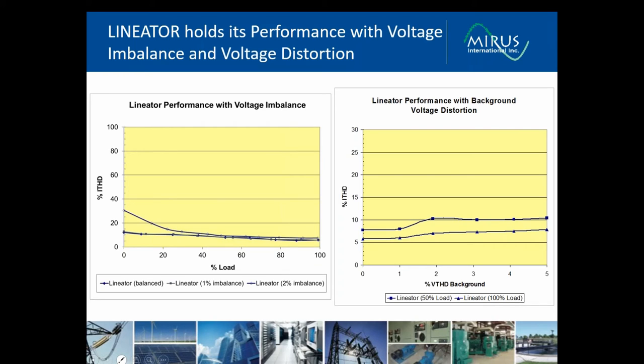We talked about the real world guarantee. Here we have, again with voltage imbalance, the performance of a filter with balanced or 1% imbalance. You can see here's our performance waveform. Light loads, THD, all the way up to full load. As we introduce 2% imbalance, there is a drop off, but it still performs within our performance guarantee, even at those higher voltage imbalance levels. And with background voltage distortion, you can see there is some drop off in performance, but even with 5% background voltage distortion, we're still within our performance guarantee of less than 8% on the standard filter.